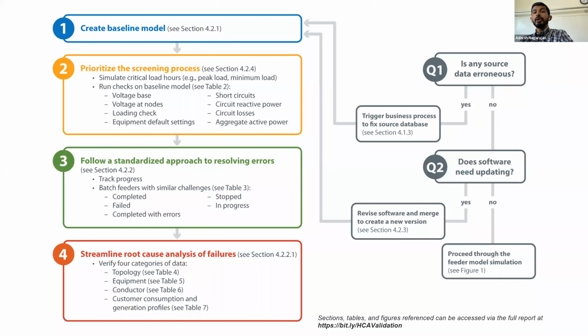You prioritize. You run selected critical hours, such as peak load, minimum load, or whatever hours you know are important to your local region. Then check for voltages, loading, circuit losses, reactive power at the feeder head, and aggregate active power consumption. Then follow a standardized process. You look at resolving errors, and you look at batching the feeders that have similar issues. Once you have batched the feeders with similar issues, then do a root cause analysis. Look at topology, equipment, conductor, and customer generation profiles.